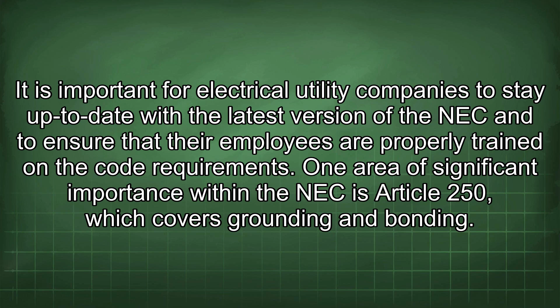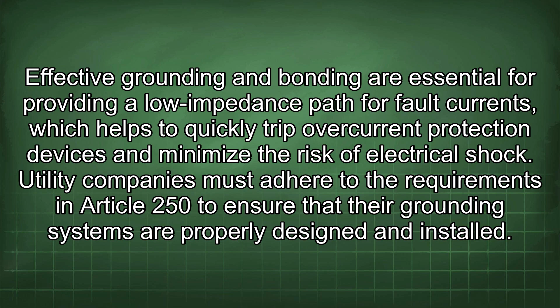Effective grounding and bonding are essential for providing a low impedance path for fault currents, which helps to quickly trip overcurrent protection devices and minimize the risk of electrical shock. Utility companies must adhere to the requirements in Article 250 to ensure that their grounding systems are properly designed and installed. Another critical aspect of the NEC for utility companies is Article 310, which deals with conductors for general wiring.